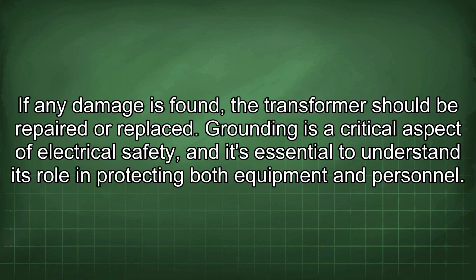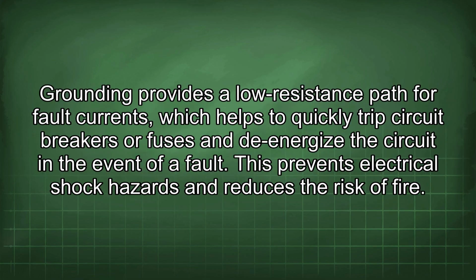Grounding is a critical aspect of electrical safety, and it's essential to understand its role in protecting both equipment and personnel. Grounding provides a low resistance path for fault currents, which helps to quickly trip circuit breakers or fuses and de-energize the circuit in the event of a fault. This prevents electrical shock hazards and reduces the risk of fire.